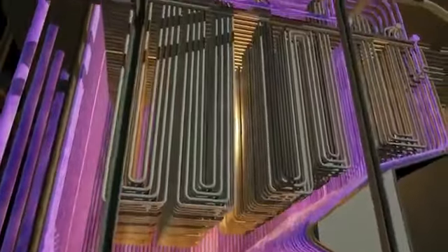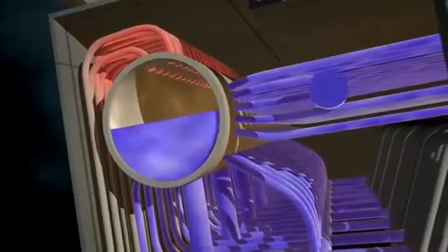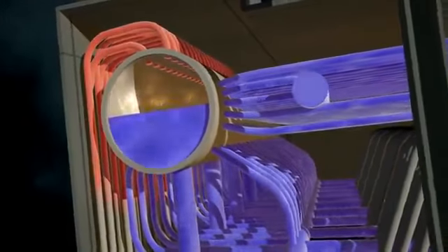A network of 2-inch tubes lines the firebox walls, and burners force feed a continuous supply of combustible fuel into the ultra-hot firebox. Eventually, the insides of the firebox burn so hot that its surrounding steel walls would melt if not for the tube-lined walls of liquid water. At the point in the cycle when the liquid water turns to steam, the steam separates and collects at the top of the steam drum.